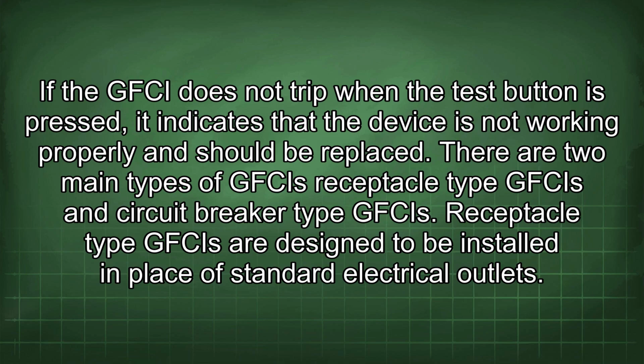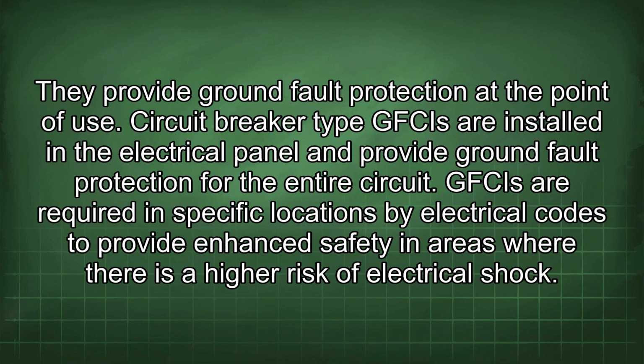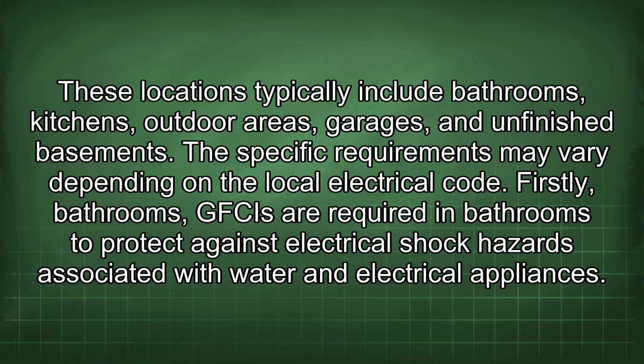There are two main types of GFCIs: receptacle type GFCIs and circuit breaker type GFCIs. Receptacle type GFCIs are designed to be installed in place of standard electrical outlets. They provide ground fault protection at the point of use. Circuit breaker type GFCIs are installed in the electrical panel and provide ground fault protection for the entire circuit. GFCIs are required in specific locations by electrical codes to provide enhanced safety in areas where there is a higher risk of electrical shock. These locations typically include bathrooms, kitchens, outdoor areas, garages, and unfinished basements. The specific requirements may vary depending on the local electrical code.